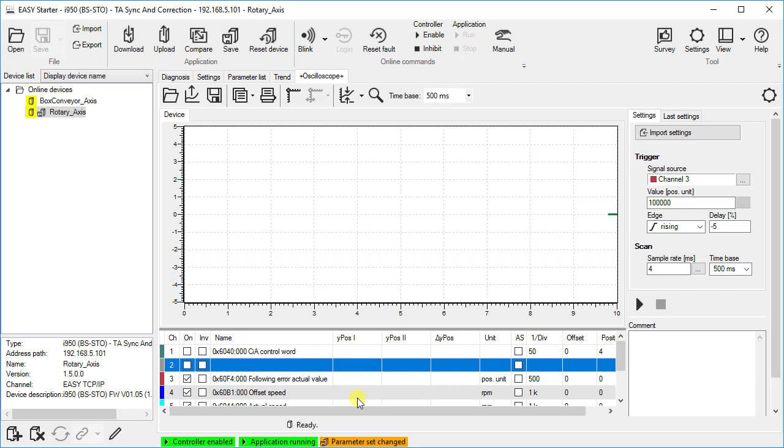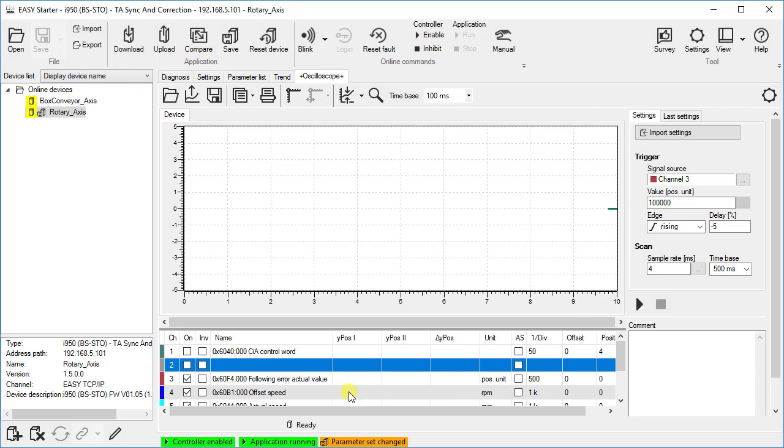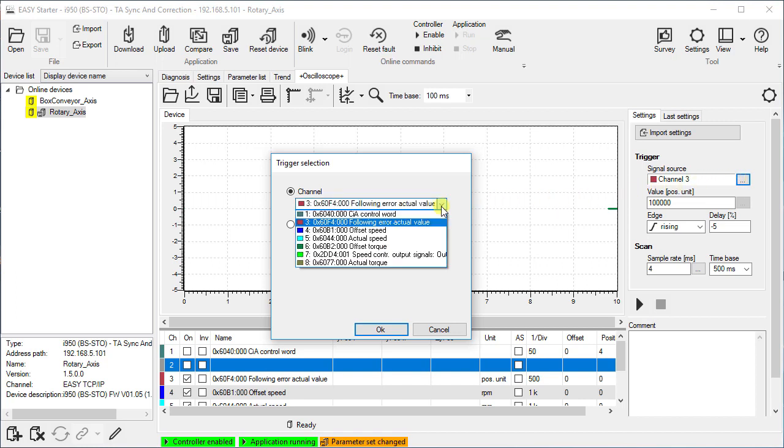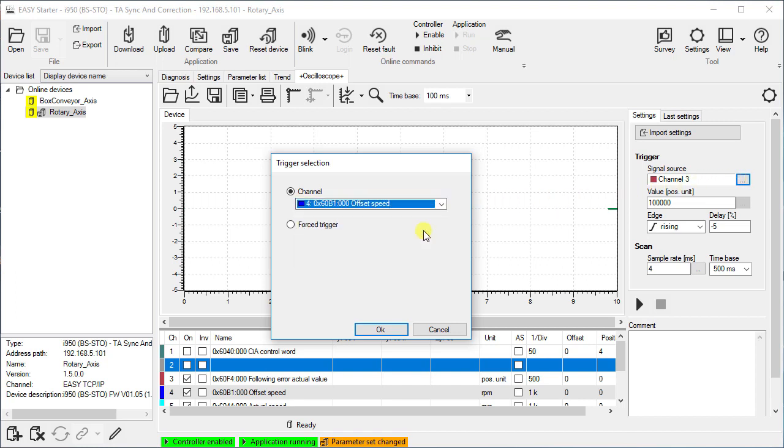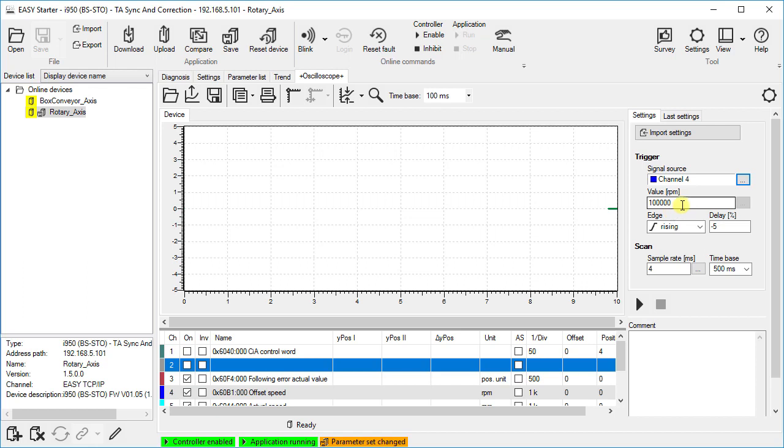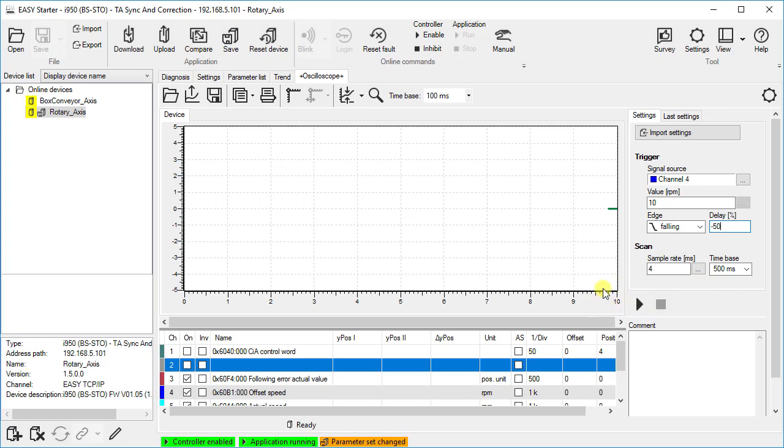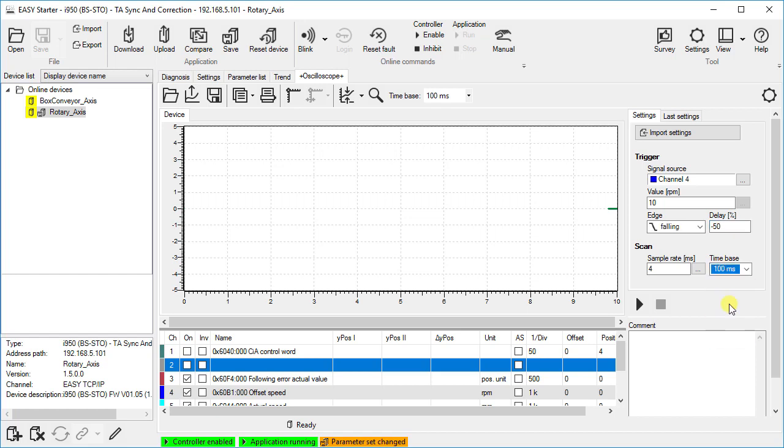In our case we want to record the measurement at the time the drive stops or comes to a standstill. Therefore, we select the channel showing the speed as signal source of the trigger. Let us set the delay time to minus 50 percent. A negative delay time activates a pre-trigger. Minus 50 percent means that half of the time axis is before the trigger event, the other half is after. The scan determines the window of the recording. The measurement duration is 10 times the time base. In our case the drive is stopped within few hundred milliseconds. A time base of 100 millisecond means that the measurement takes 1 second in total.